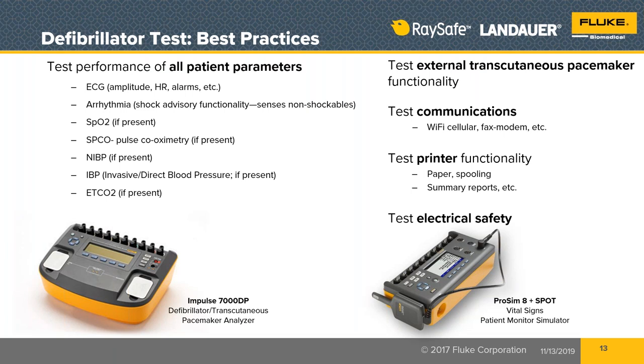But there's more to a defibrillator than just the defibrillator or the pacemaker. The defibrillators today, especially the advanced cardiac life support ones, are including everything that's in a patient monitor today. So that's the ECG, certainly. It's arrhythmia determinations like shock advisory or AED functionality. There's pulse oximetry, or in the case of emergency services and air medevac, we're now seeing a lot more of the pulsed co-oximetry. That's like Masimo Rainbow. So that's SpCO. And you need to have a test instrument capable of doing the functional test for that pulsed co-oximeter. You cannot do it with a regular oximeter tester.